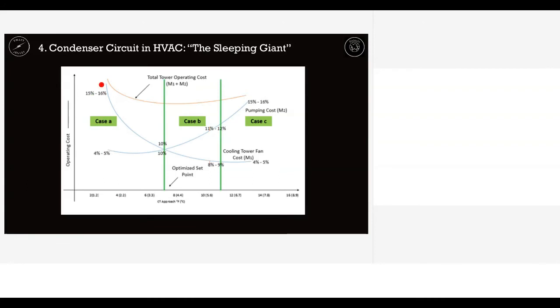And the chiller load, the centralized air conditioning chiller load, should not be more than 70%. That is another boundary condition, because the higher the load, the higher the amount of heat that will be developed in the condenser of the chiller. There will be more hot surface developed, and it can create scaling issues in the chiller. But load is also a boundary condition. Still, if the cooling tower approach is high, the pump frequency should be less, and the cooling tower should do more.